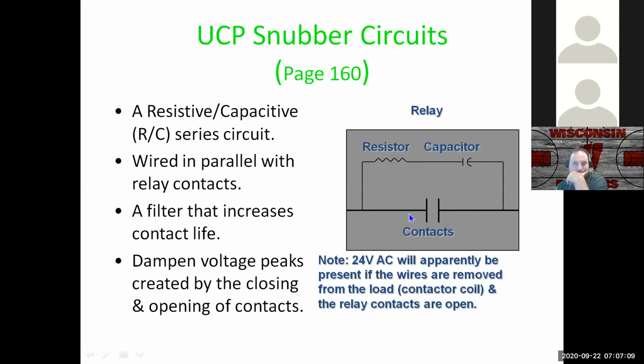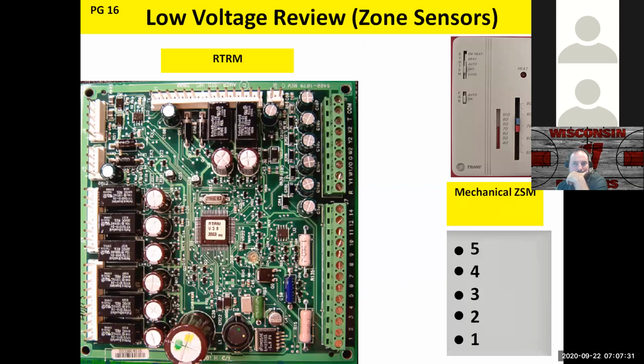So when you're checking voltage on these units, make sure the load is connected, and it won't give you some false readings if you're aware of this particular circuit in there. And it's on a lot of the circuits. So if you unplug a compressor contactor or fan contactor, you may see phantom voltage there that is going to give you some false readings. So, just be aware of that.